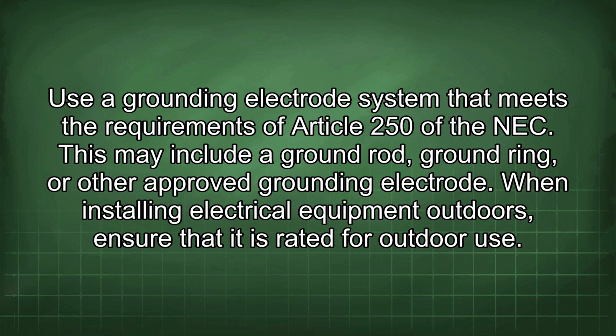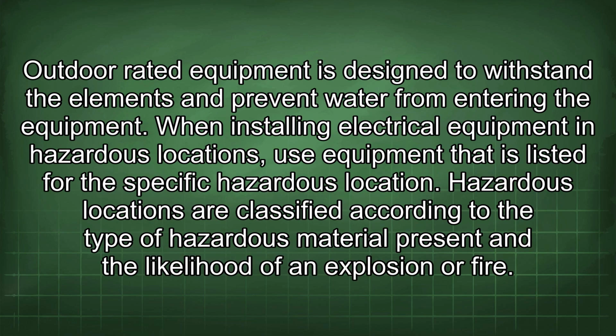When installing electrical equipment outdoors, ensure that it is rated for outdoor use. Outdoor rated equipment is designed to withstand the elements and prevent water from entering the equipment. When installing electrical equipment in hazardous locations, use equipment that is listed for the specific hazardous location. Hazardous locations are classified according to the type of hazardous material present and the likelihood of an explosion or fire.